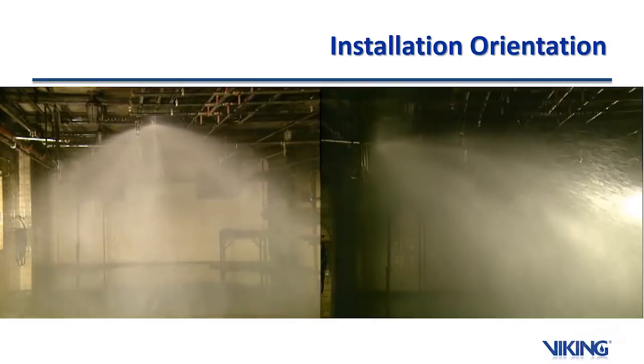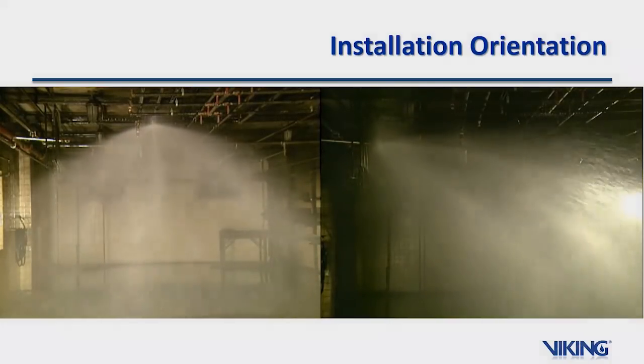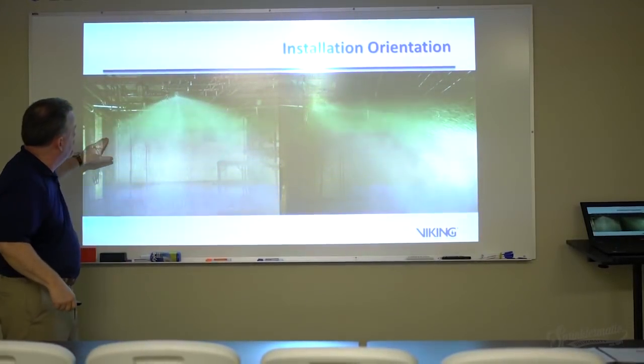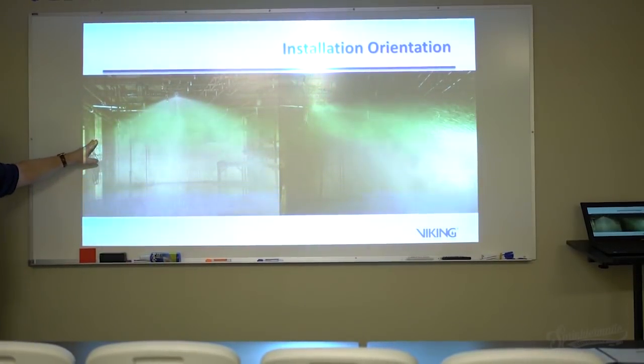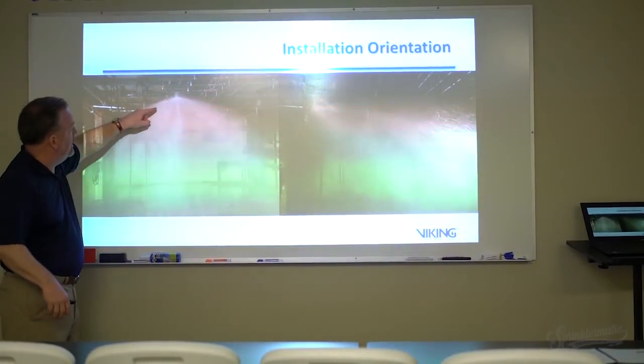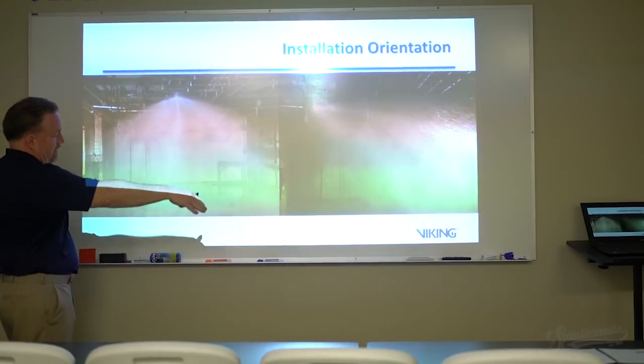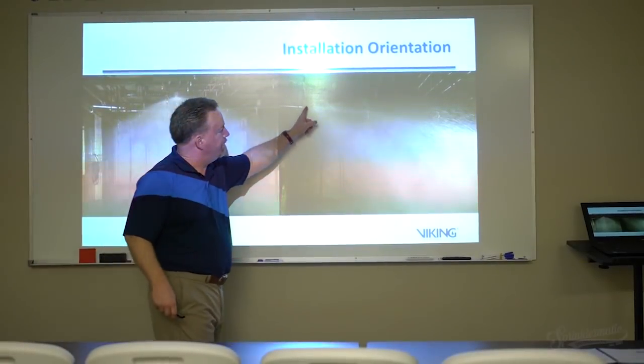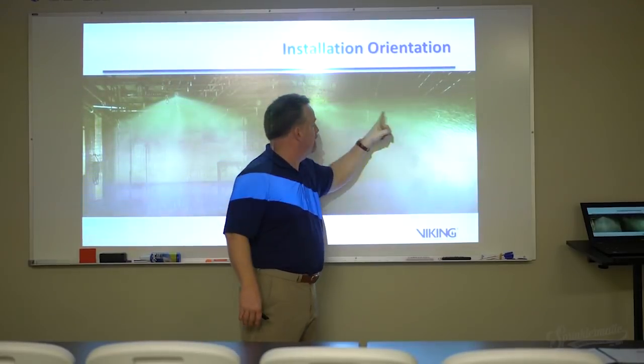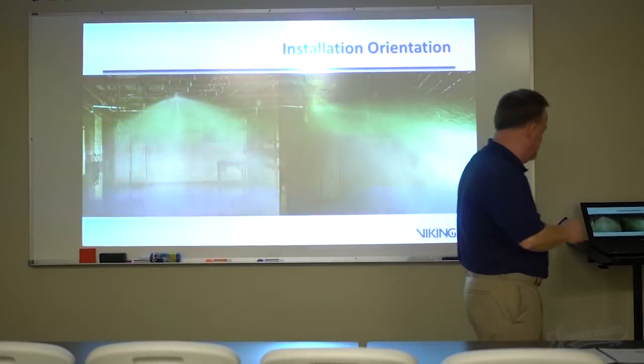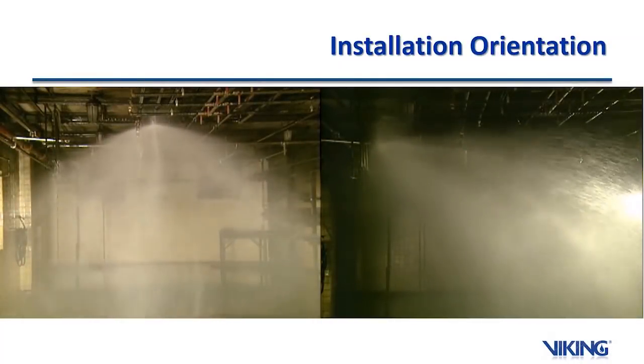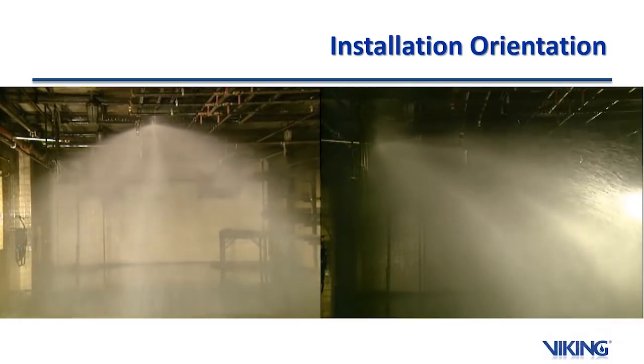Here are spray pattern examples. The standard spray pendant sprinkler creates a fairly conical shape directing water straight down into the protected floor area. The sidewall sprinkler, on the other hand, shoots water out as far as it can reach based on the deflector and pressure. An upright sprinkler in the same area would show the same kind of conical spray pattern as the pendant.